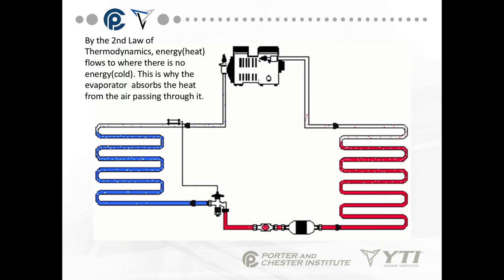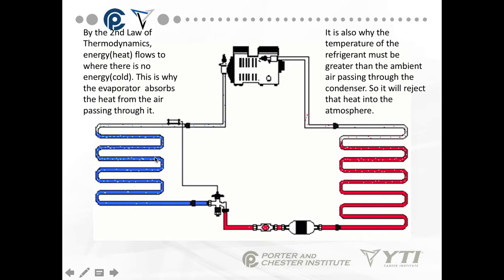The second law of thermodynamics says that heat, which is energy, flows from an area of high energy to an area of low energy — from hot to cold. That's why the evaporator absorbs heat from the air passing through it. If I blow warm air across the evaporator coil, the heat is absorbed into the coil because there's a lack of energy inside the coil. It's also why the temperature of the refrigerant must be lower than the ambient air on the evaporator side.